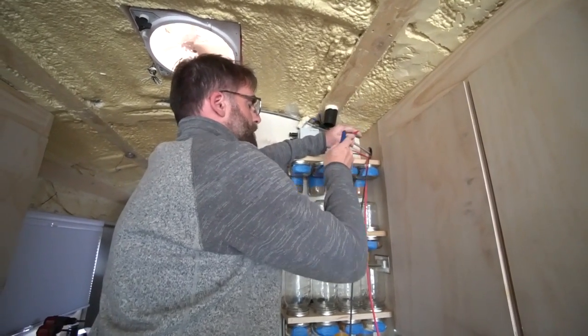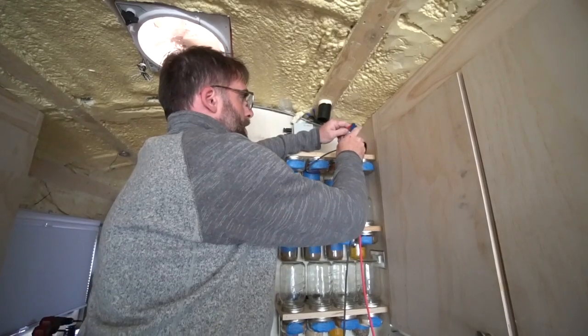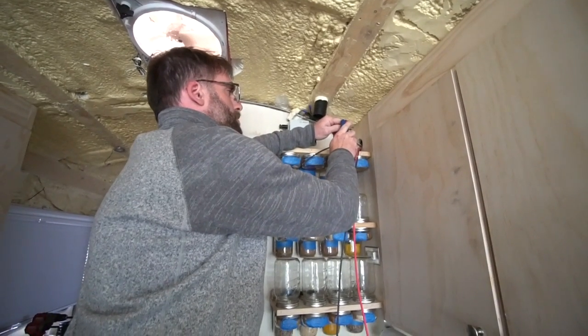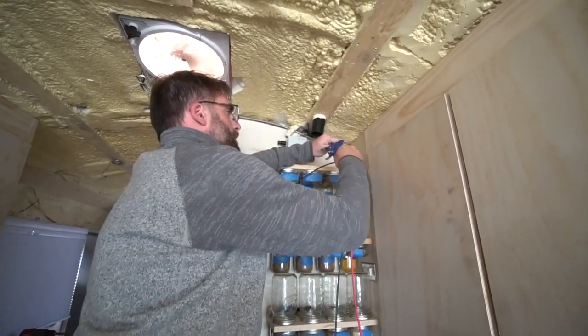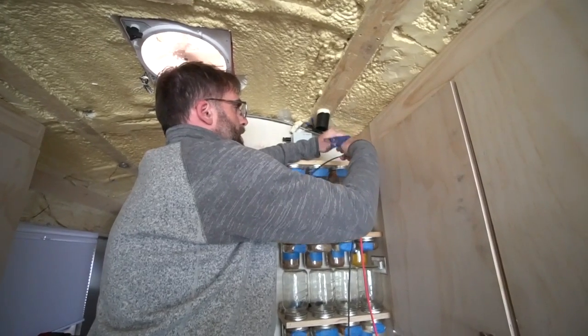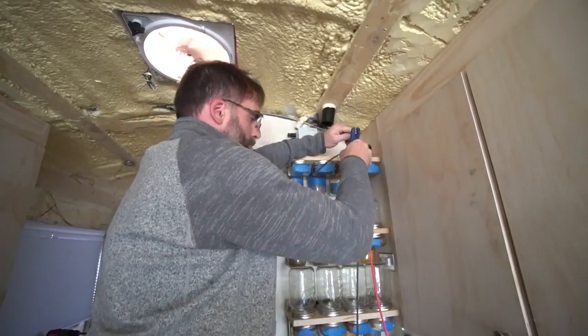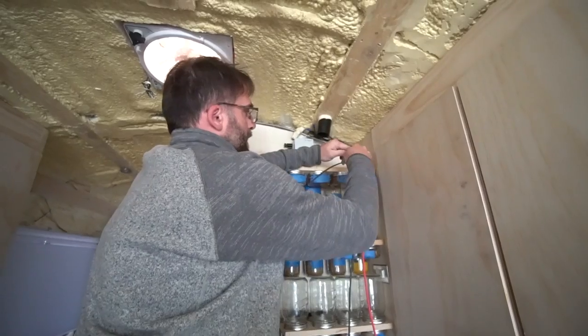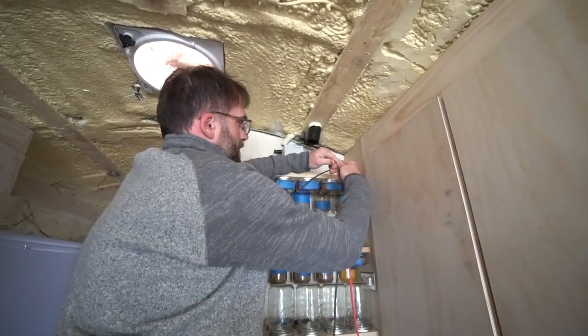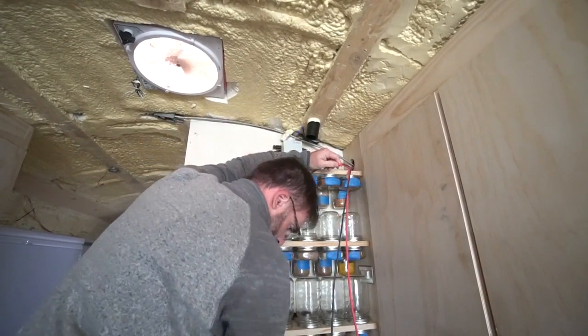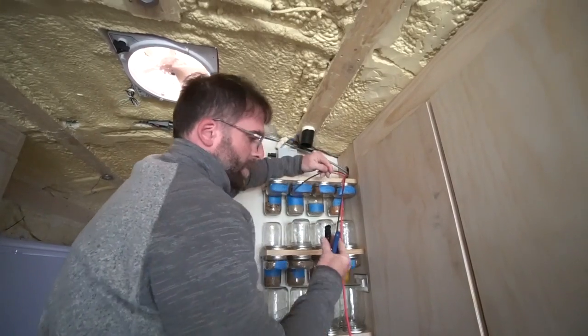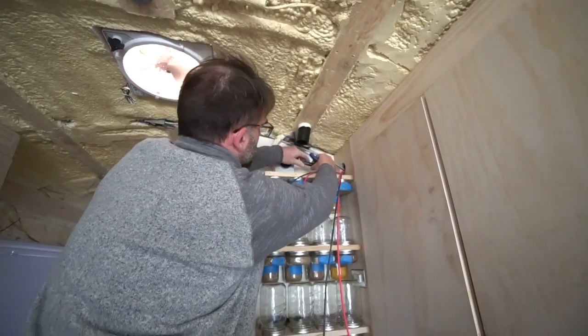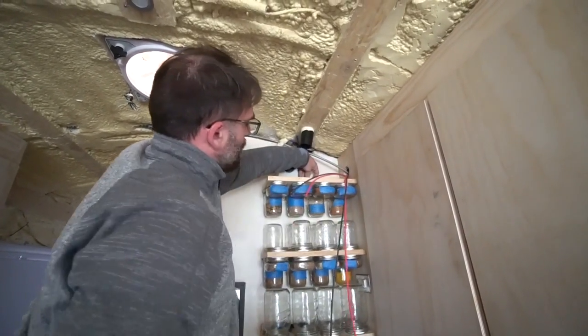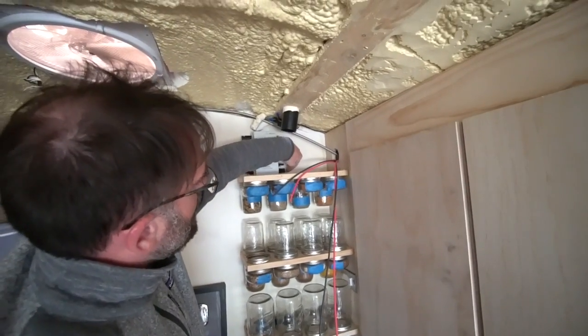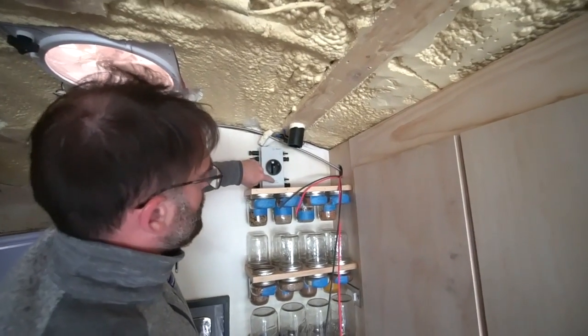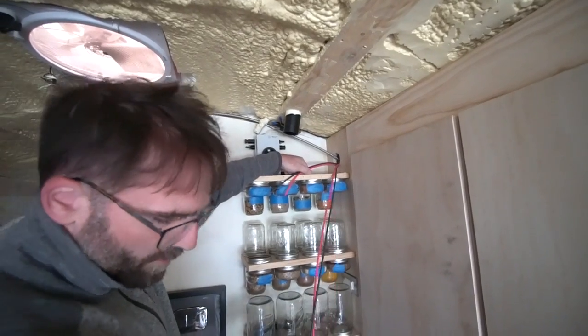Talk about the system as coming from the combiner and the electrical equipment, and then going to the solar panels in this case. MC4 connectors are polarized. There's a male and female side, and you need to make sure that you maintain the correct ends on all of them. So I am terminating a male output end, so that's going to go right into there, and then we'll have a negative output end. So this is PV array number 2 is this one, and PV array number 1 is this one.